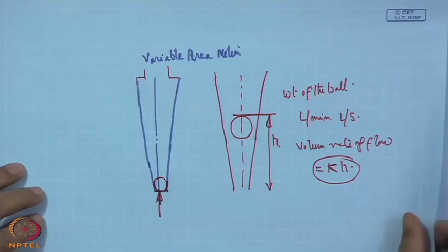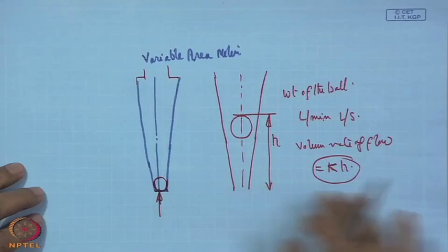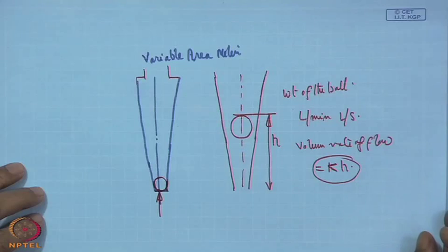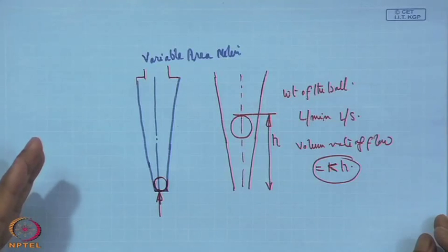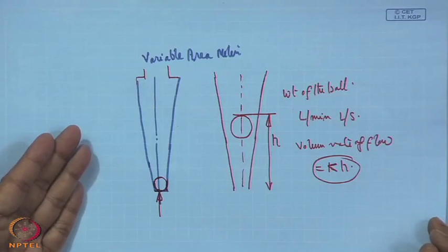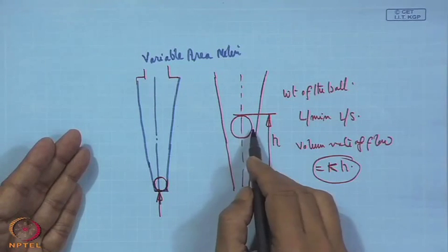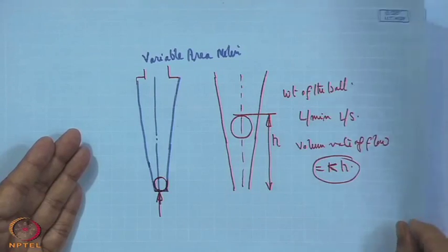And this is actually a rotameter, and since it also keeps on rotating because of the gas flow, that is why it is called the rotameter. So, it is basically a float which keeps on floating under the action of the viscous flow, the buoyant force and the weight, and accordingly this annular passage will keep on increasing and the flow rate will keep on increasing. Now comes the mass flow controller.